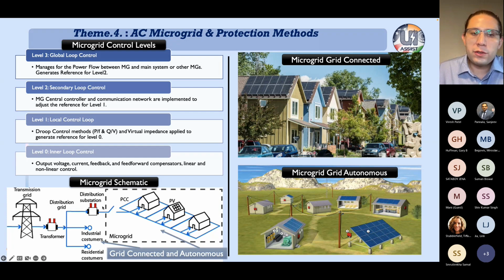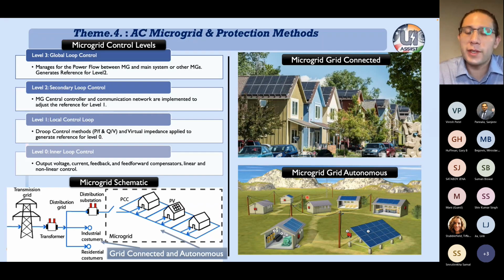The bottom left figure shows a microgrid, which can be grid connected or autonomous. Here we can see how we represent the point of common coupling when the microgrid works in autonomous mode and in grid connected mode. The two figures on the right-hand side exemplify a microgrid connected to the grid, and also autonomous, basically independent, like in a small village in a very remote area. The grid connected mode can be a small neighborhood in a very populous city.